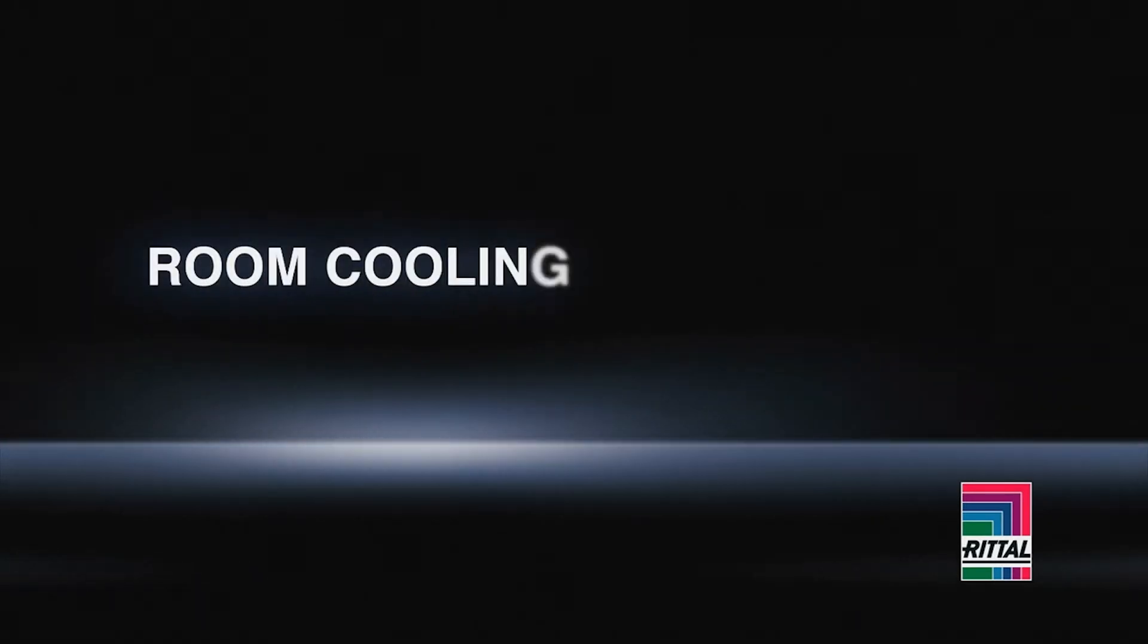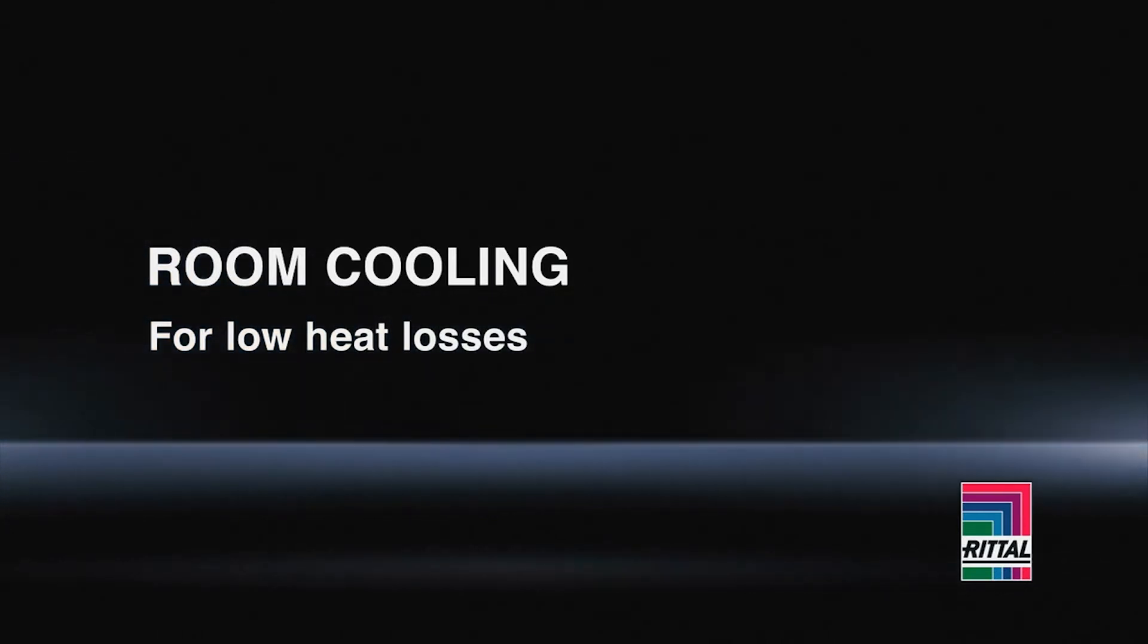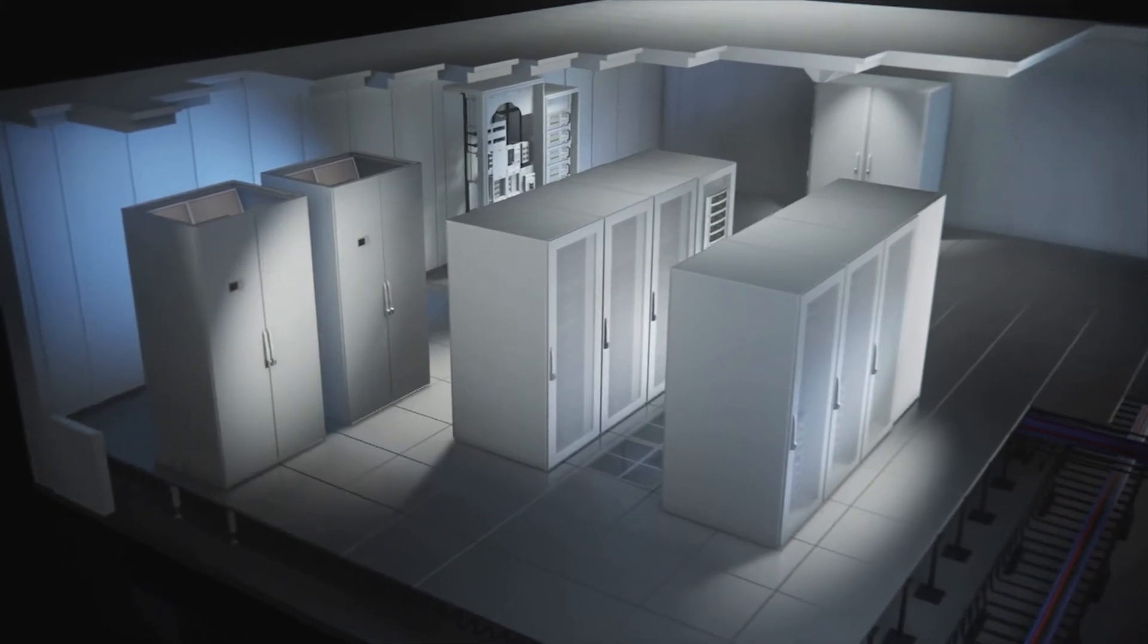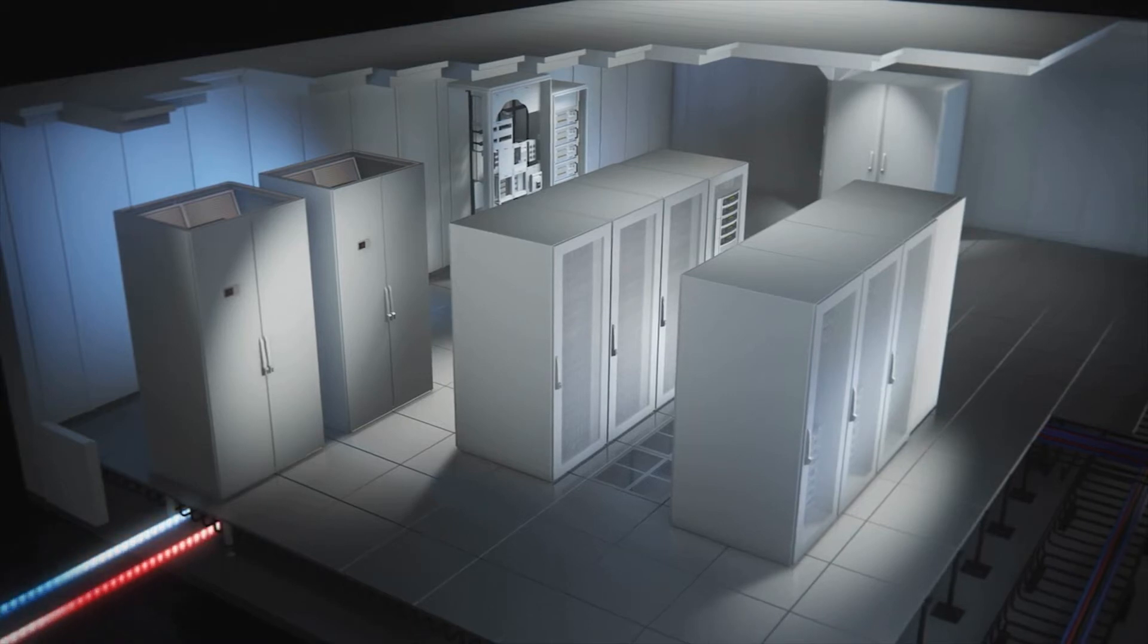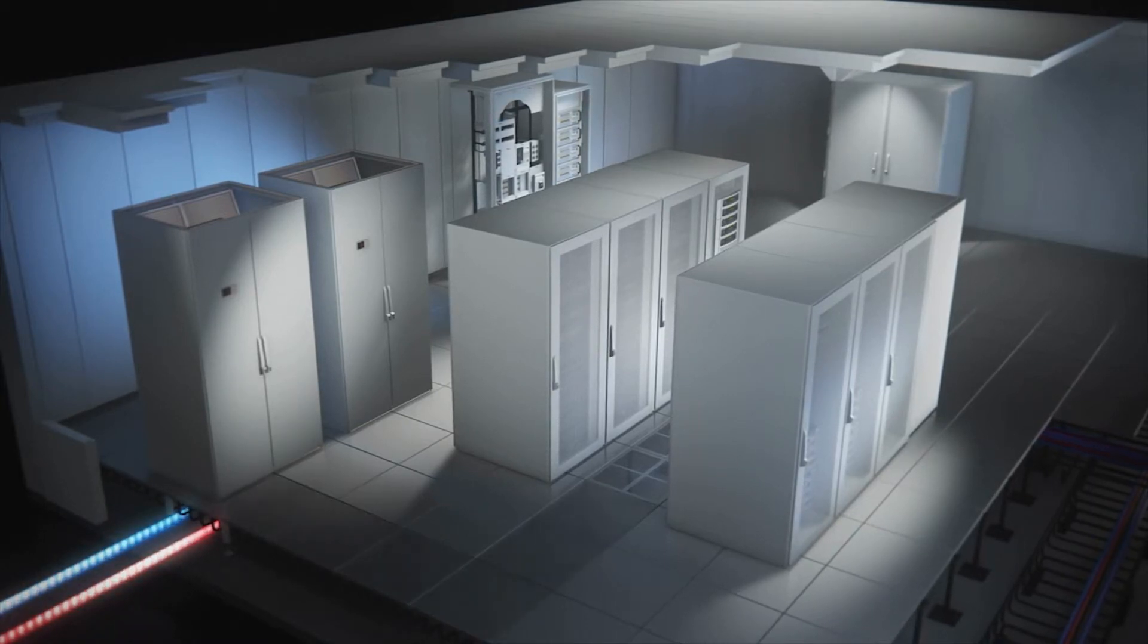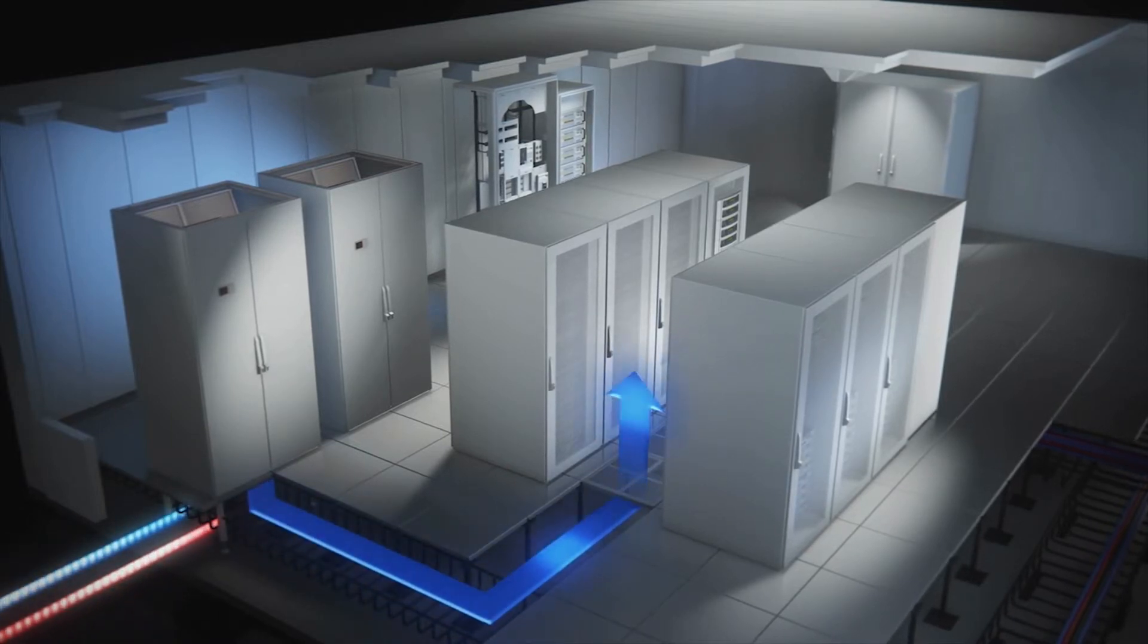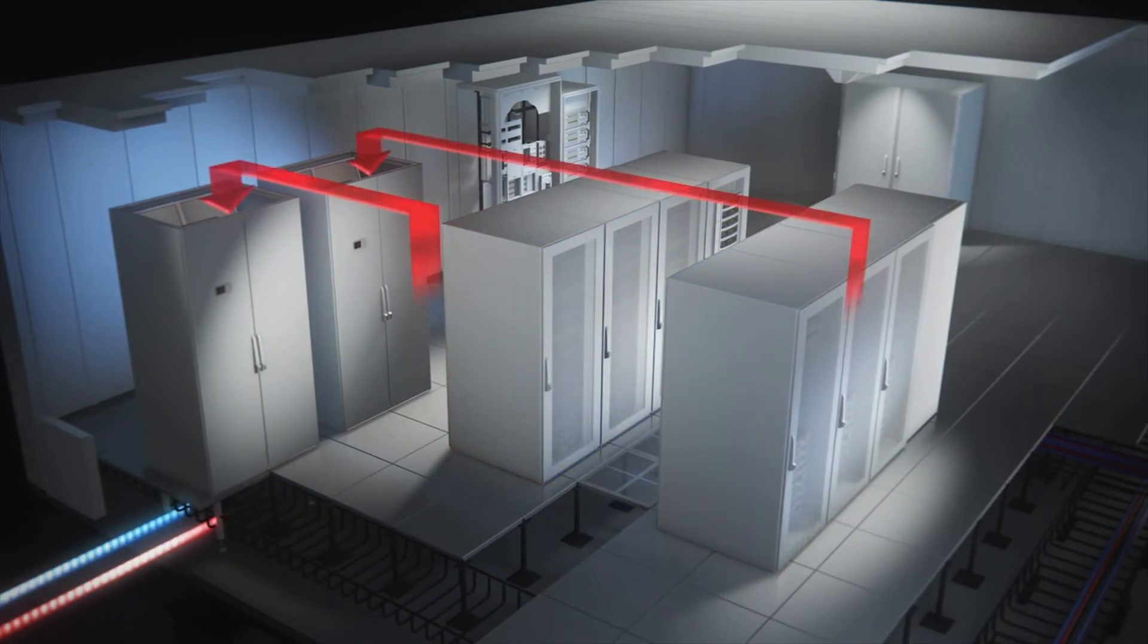Room cooling is ideal for installations with smaller heat loads and low levels of heat loss. Computer room air conditioners are inside the IT center and have their own cool water and warm water lines. Cold air is fed beneath the raised floor and up into the room through vents in front of the server enclosures.